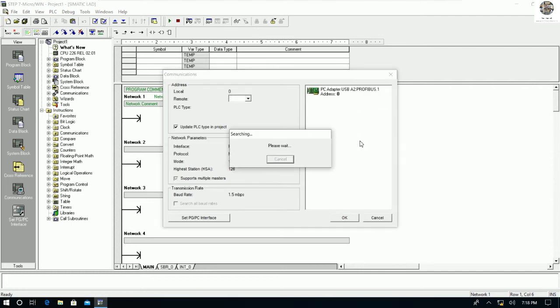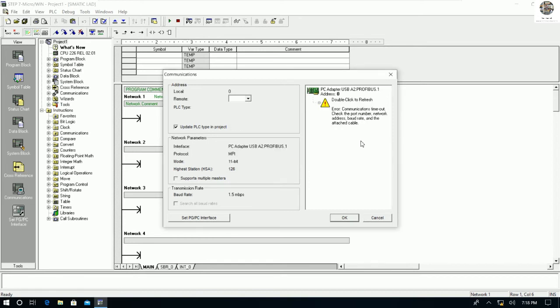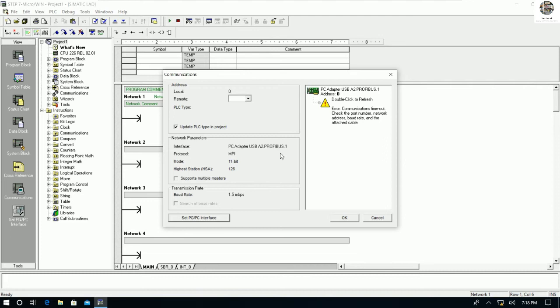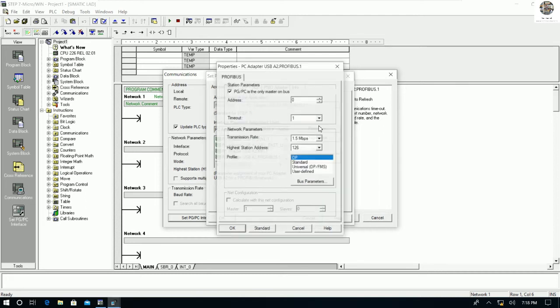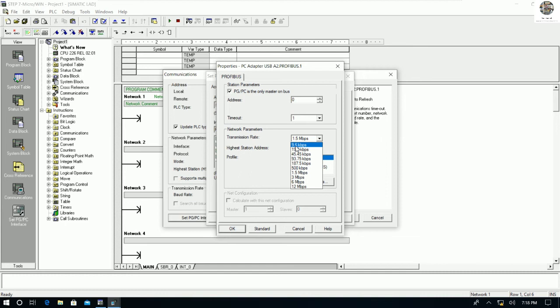An error occurs because the baud rate does not match — it is not the same as the baud rate configured on the PLC. We need to choose a baud rate that matches the PLC's baud rate. From my experience, I will use 9.6 kilobits per second for communication.